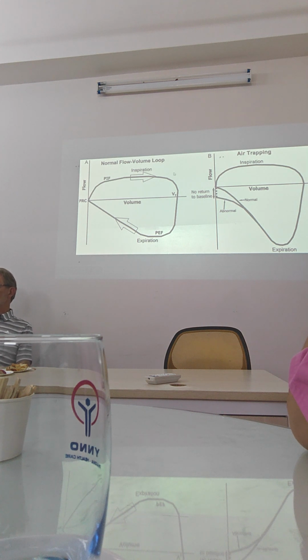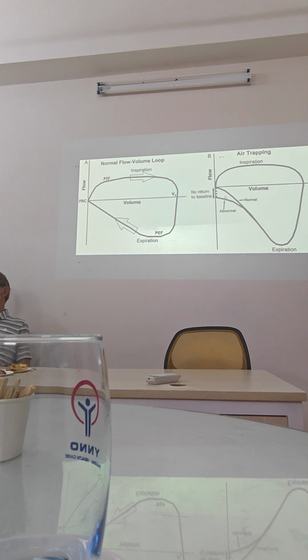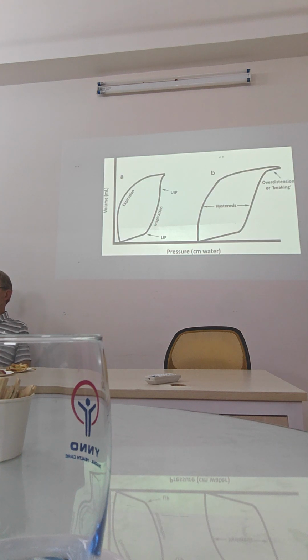So there are certain circumstances where this gives you a lot of information. In your normal flow volume loop, you always come back to 0. If you have a flow volume loop that doesn't come back to 0, there's no return to baseline. What that means is that some of the volume of gas has stayed trapped in the lungs, in gas trapping. The other loop that's really helpful is the volume pressure loop. And there are 2 parts to this. With good compliance, the volume pressure loop has a slope of about 45 degrees. With poor compliance, it sits down much flatter. So you can get an idea of whether the surfactant's been helpful.